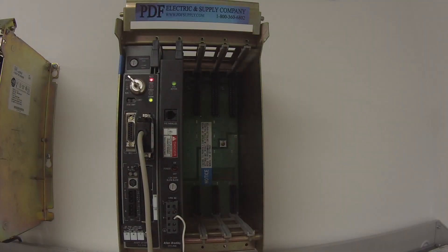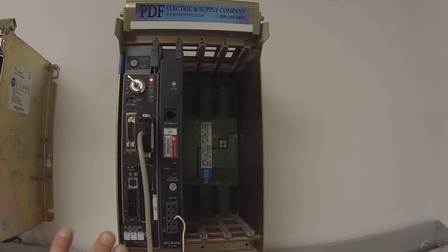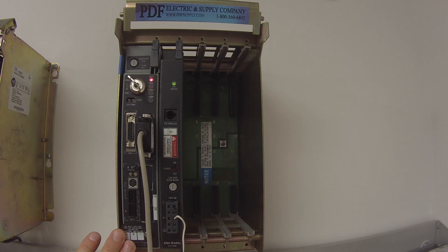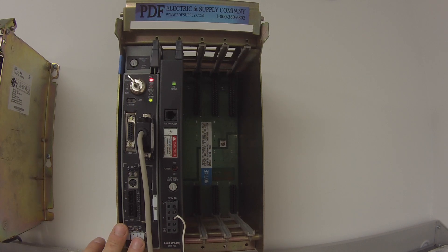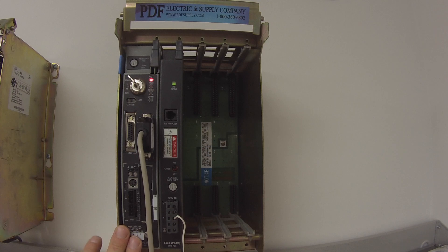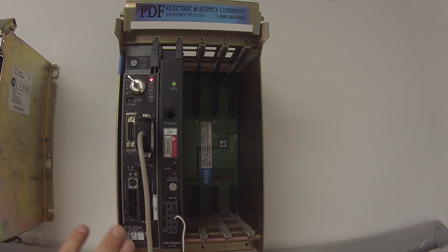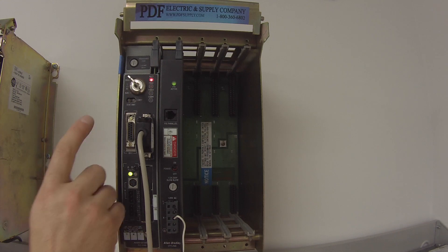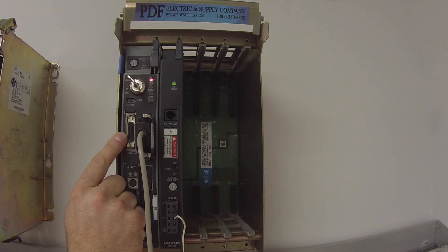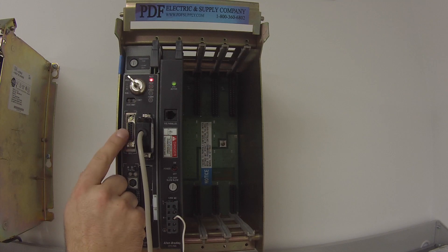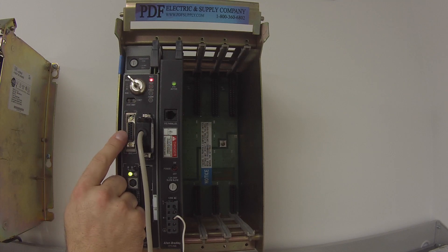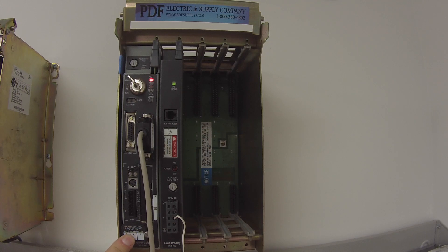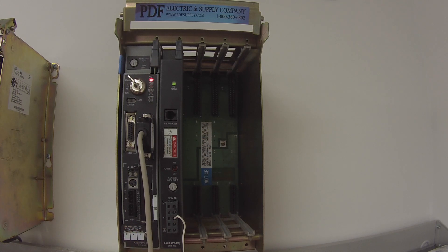Now would be a good time to tell you that this processor I have here has a battery that's been tested good. I say this particularly on the ethernet modules, of course you should always have a good tested battery in these processors, but in the instance that you remove the processor and you're testing it solely, if you've configured an IP address, sometimes you need to power cycle in order for that IP address to take, so it would be good to have a battery that's in good working order or actually a must, so just make sure that that's working properly.